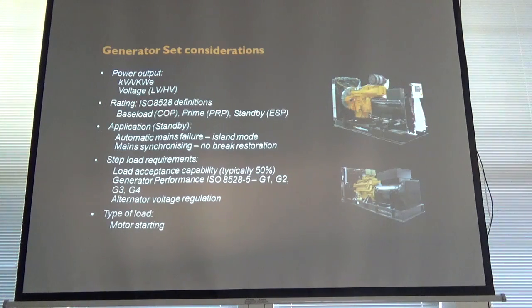If you're saying G3, and you're starting, you know, it's your starting system and the amount of load you're putting on in each complete step, which in turn affects your unit. If you're giving me a performance criteria or a maximum dip in voltage or frequency and recovery time, that in turn affects the engine alternator combination. I don't think anybody in this room goes through all that. Well, basically, we all oversize it. Yeah, but to be frank, we all do it. You're being safe by doing that.